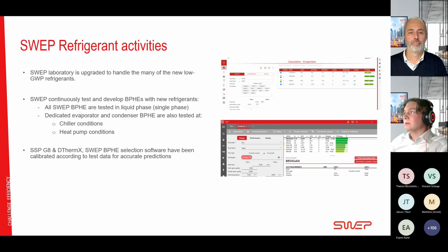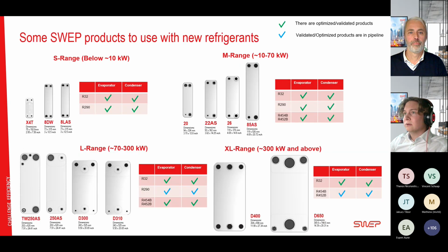Let's see, I'll take control so I can switch slides. So in this slideshow, I will present some products that work with these new refrigerants that we have been speaking about. And I would like to start with introducing the S range, which is our small range that will have capacities typically around or below 10 kilowatts. And the BPHEs that we have here are typically used in smaller residential heat pump applications. It could also be used for economizers. And here we have done proper testing with, for example, R32 and propane or 290.